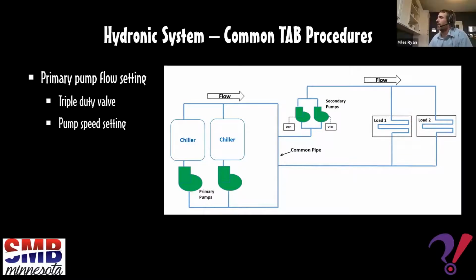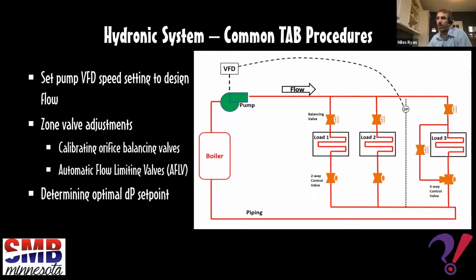All right, and how about if there's a variable speed drive on those primary pumps? Instead of using a triple duty valve, would you be adjusting the speed of that pump to bring down the flow? If there was a VFD, yes, that's what we would do. All right. How about on the secondary or the variable speed?